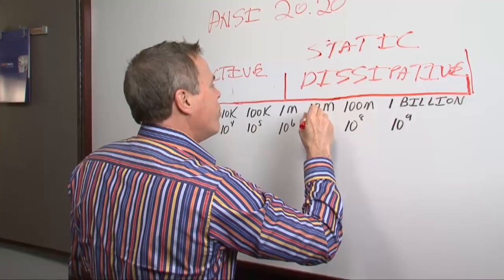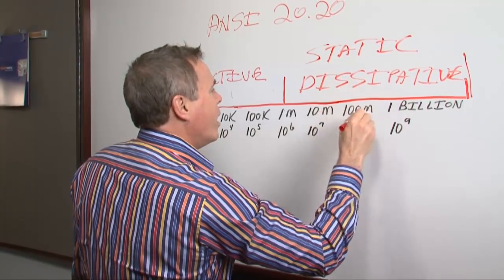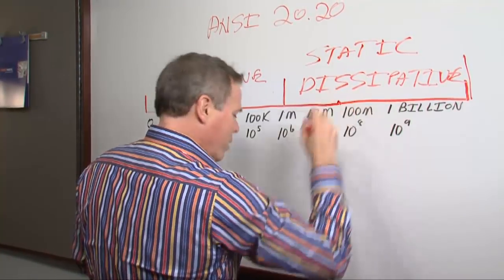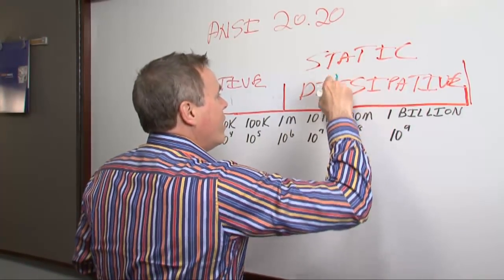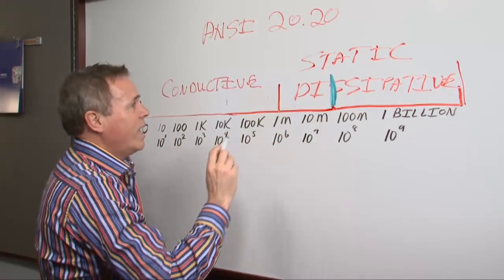ANSI 20.20 says that the floor and the person together should have a resistance of less than 35 million ohms. Well, 35 million ohms is somewhere in between 10 million and 100 million. So let's call it right here. And let's use the green marker. And we'll say that that's the highest point of resistance we can have.